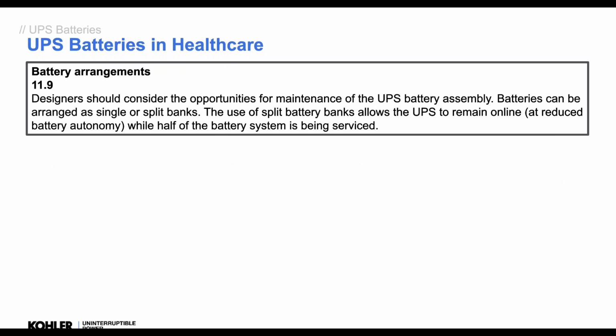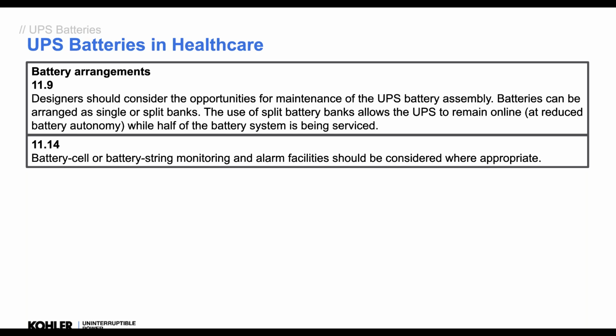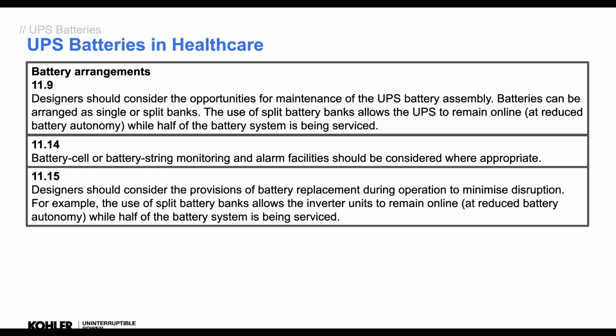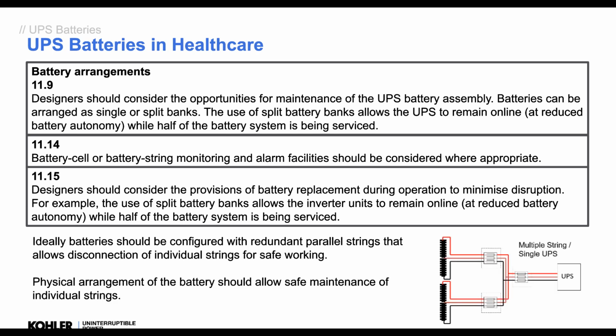Talks about battery arrangements, making sure you can split the battery. Talks about battery string monitoring and alarms where appropriate. It talks about the split battery to minimize disruption. So what they're talking about is having multiple strings of batteries and some monitoring on it. This is more for resilience than maintenance, because typically we're not going to take off one string of batteries during operation, carry on running with reduced autonomy. That's typically not going to happen in a hospital environment. But if you have multiple strings of batteries, we have some resilience. If we do have a battery failure in one string, the other string will still be there to back it up. So it's much more of a resilience thing than a maintenance thing.